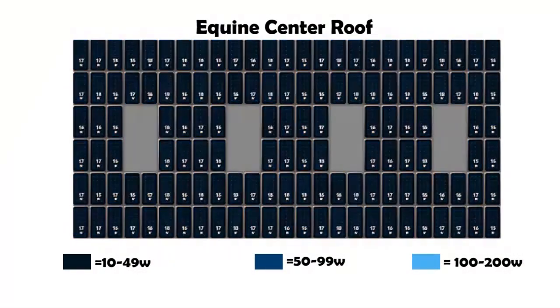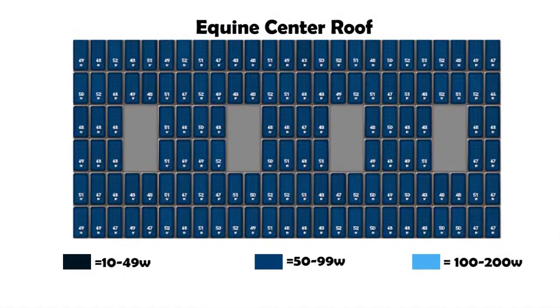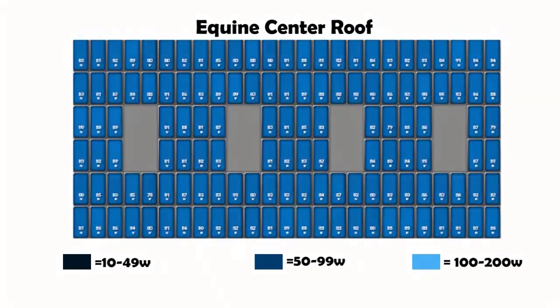The other thing too is, with this particular microinverter system, we can see real time the output of every panel through an online monitor throughout the day. So this phenomenon I was telling you about, for instance, partial shading, you can actually see that in an array. So this helps in debug. If an inverter fails, we can look immediately on that map and figure out which one it is.